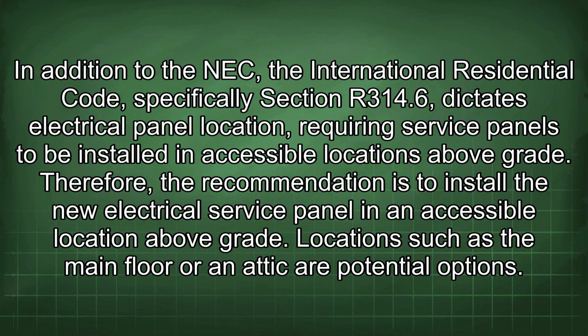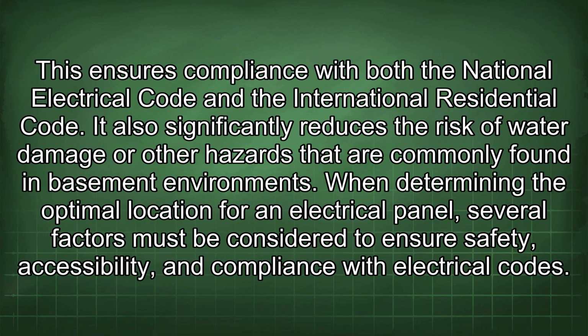R314.6, dictates electrical panel location, requiring service panels to be installed in accessible locations above grade. Therefore, the recommendation is to install the new electrical service panel in an accessible location above grade. Locations such as the main floor or an attic are potential options. This ensures compliance with both the National Electrical Code and the International Residential Code, and significantly reduces the risk of water damage or other hazards commonly found in basement environments.